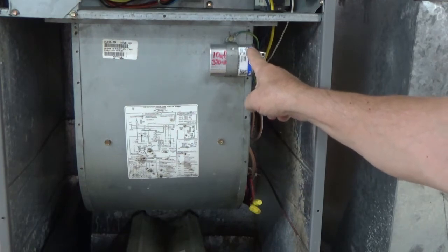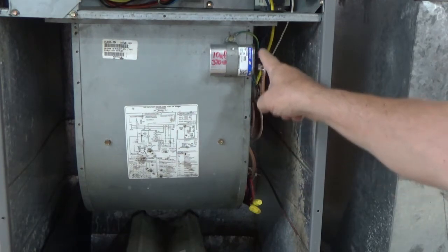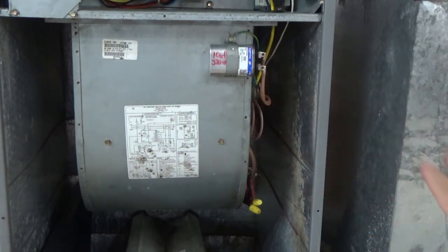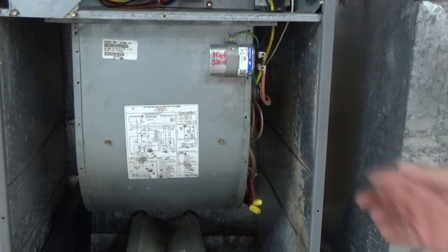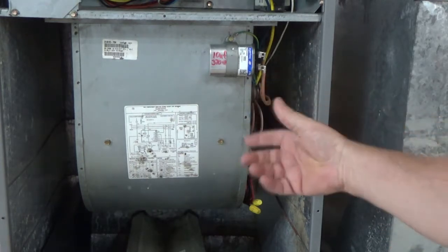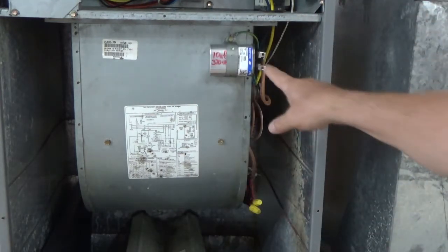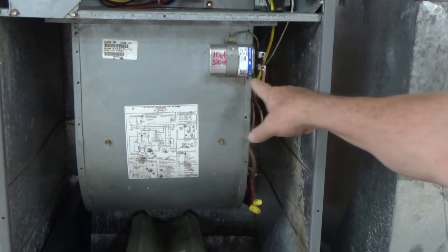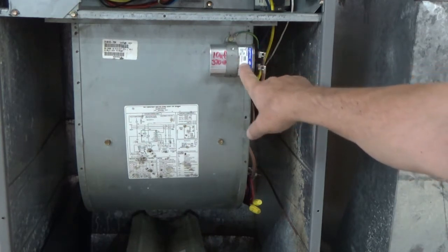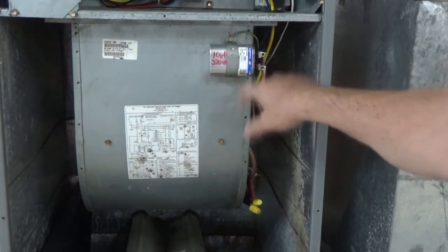If the end here is bubbled up, it may be going bad. Or if the fan's not coming on and everything else seems to be working, but the motor isn't rotating - you don't hear it firing it up, and you see that it's all bulged right here - odds are you need a new start capacitor. That's the telltale sign.